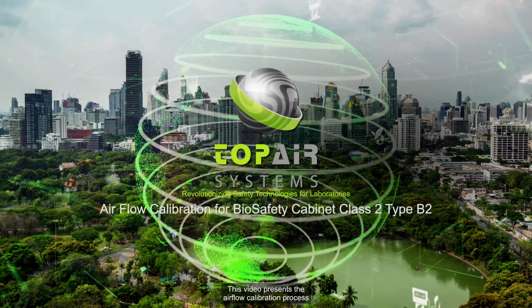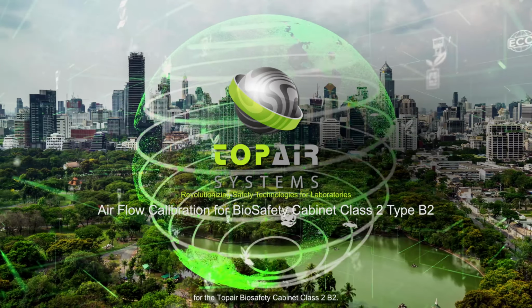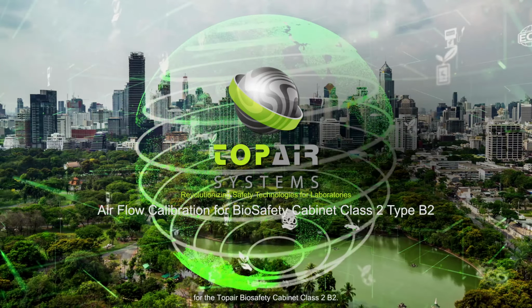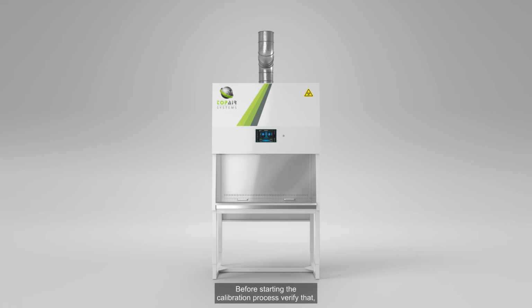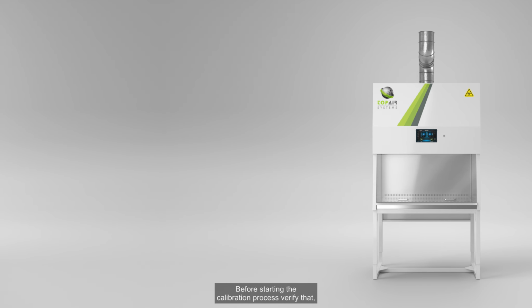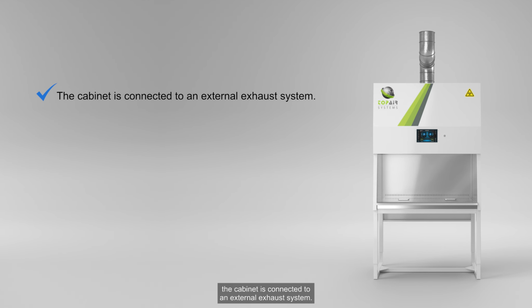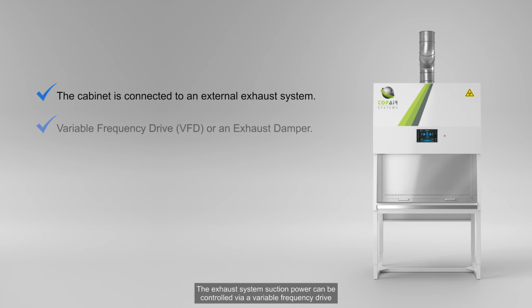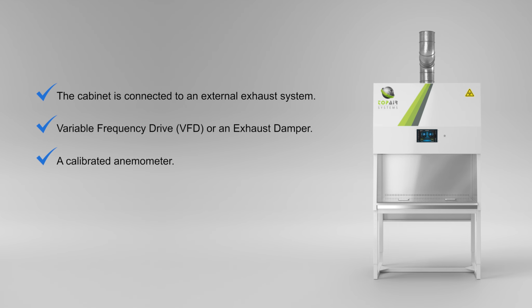This video presents the airflow calibration process for the TopAir BioSafety Cabinet Class 2, B2. Before starting the calibration process, verify that the cabinet is connected to an external exhaust system. The exhaust system's suction power can be controlled via a variable frequency drive or an exhaust damper. And you have a calibrated anemometer.